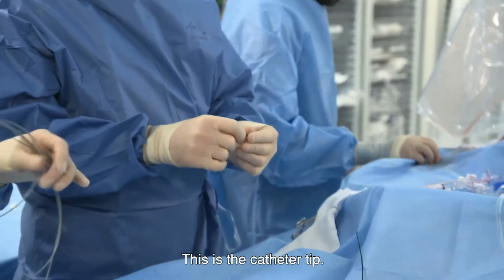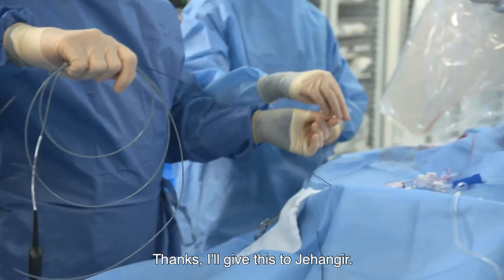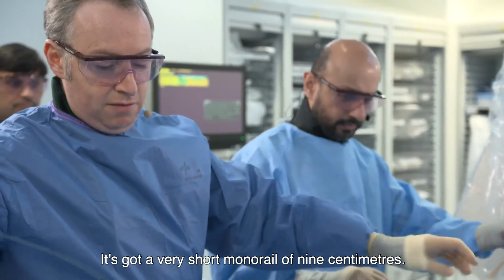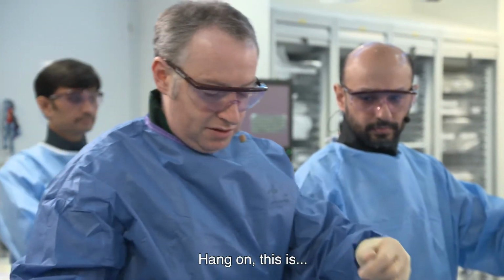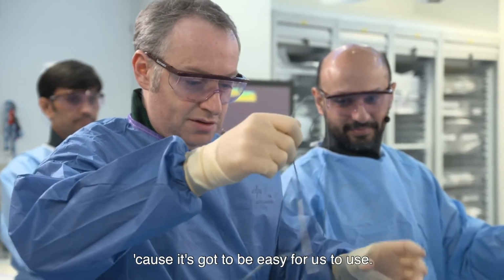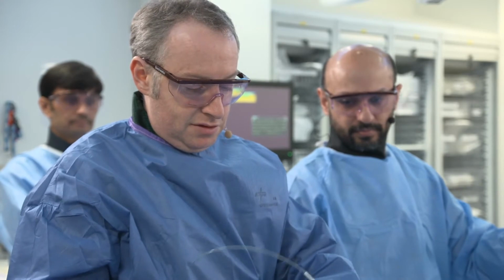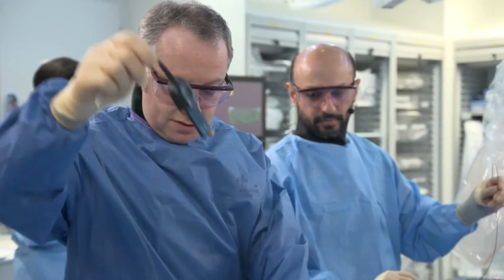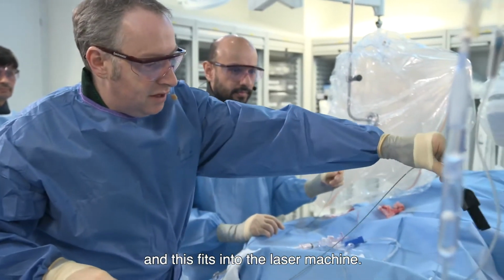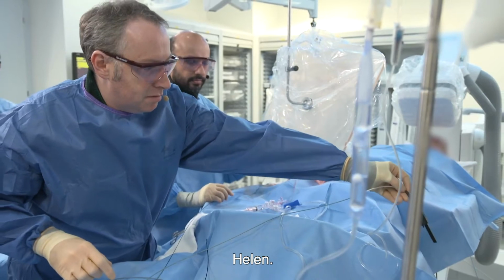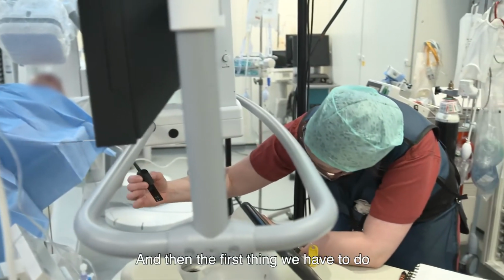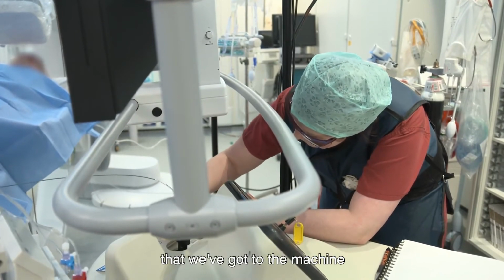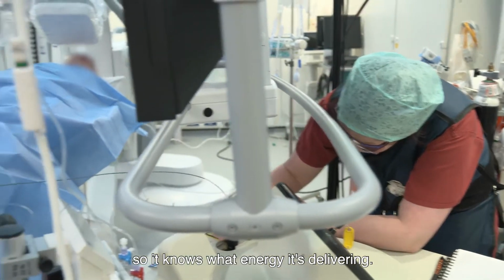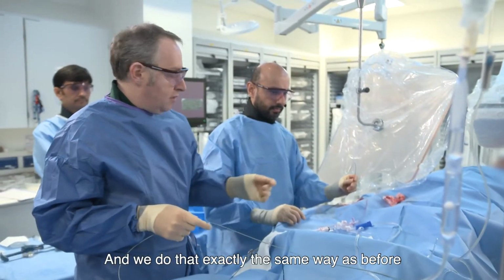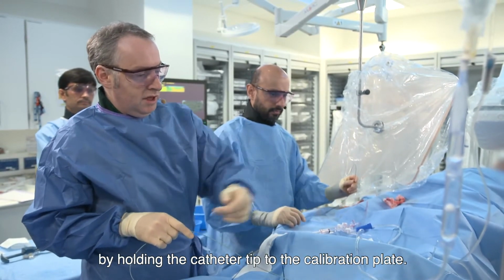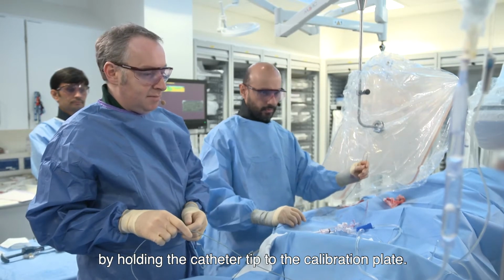So this is the catheter tip. Thanks. I'll give this to Jahangir. It's got a very short monorail of 3 centimeters. Oh, hang on, we don't want to tangle this up because it's got to be easy for us to use. Right, good. So this is called the proximal coupler, and this fits into the laser machine. Helen? And then the first thing we have to do is calibrate this specific catheter that we've got to the machine so it knows what energy it's delivering. And we do that in exactly the same way as before by holding the catheter tip to the calibration plate.